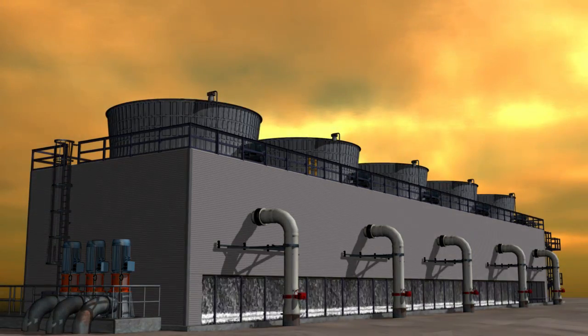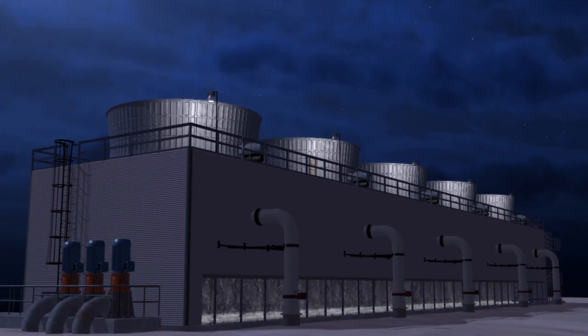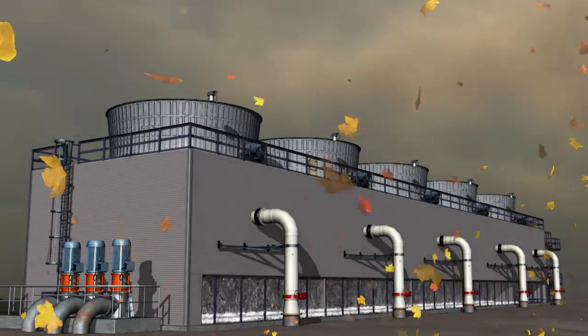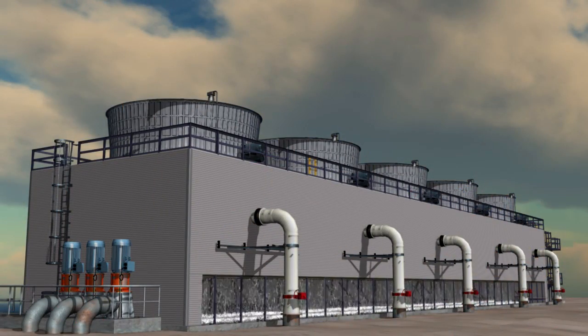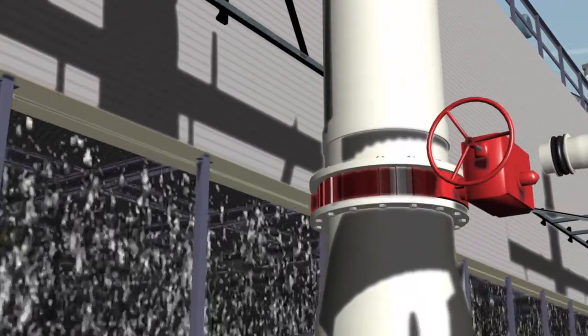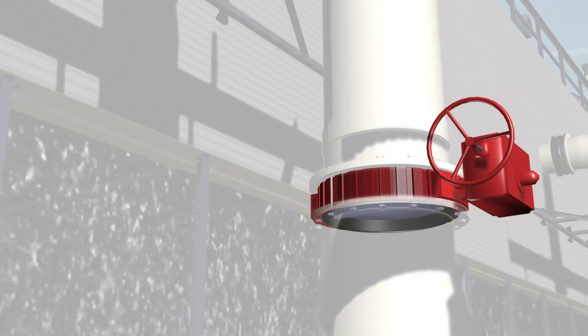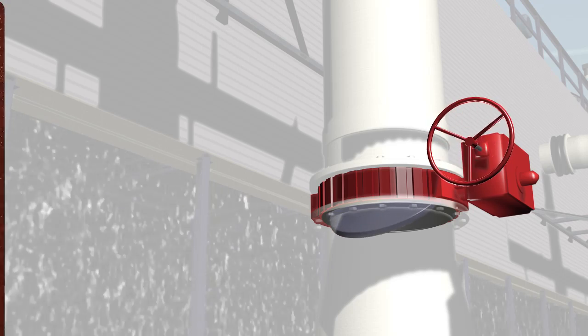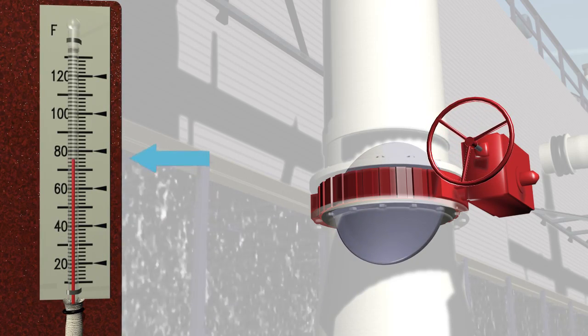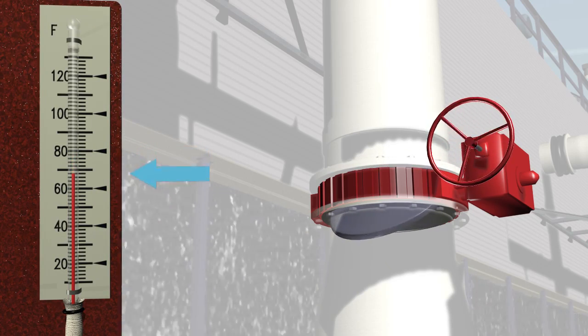The weather cools in the evening and at night. Fall and spring bring much cooler temperatures. As the wet bulb temperature drops, the tower performance will increase. Flow control valves located at each cell are often corroded and inoperable. Opening and closing valves while tracking the wet bulb up and down is both impractical and economically unfeasible.